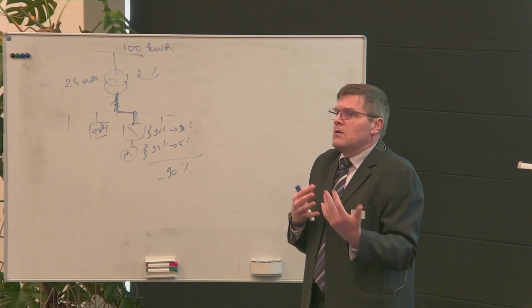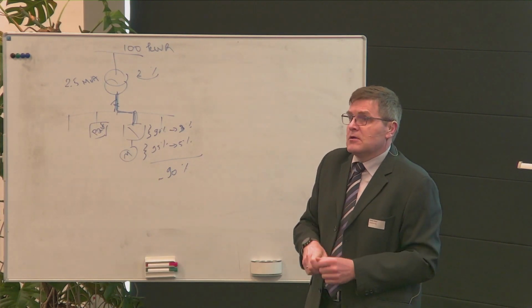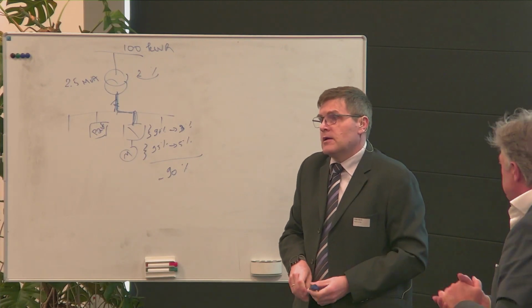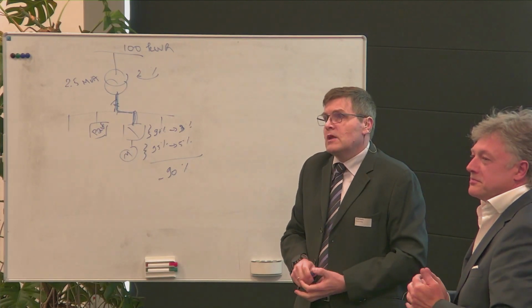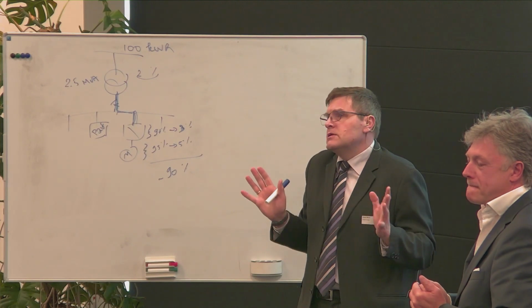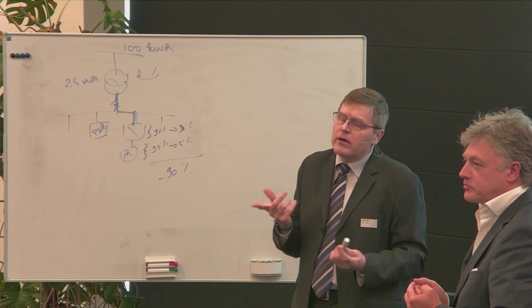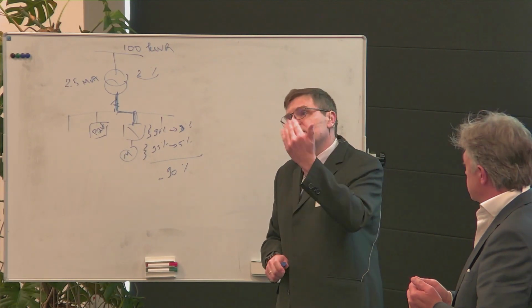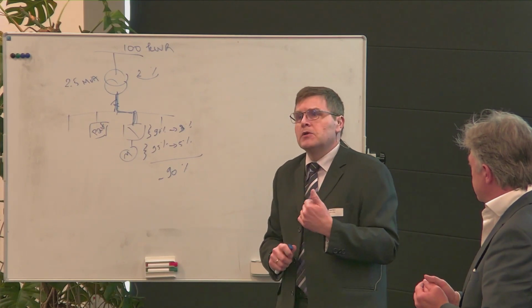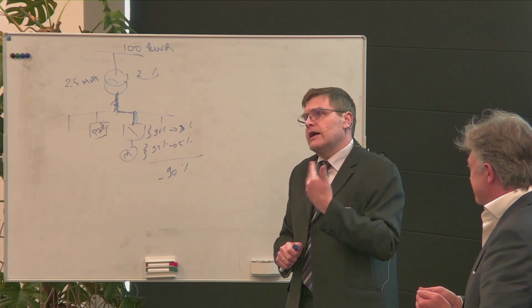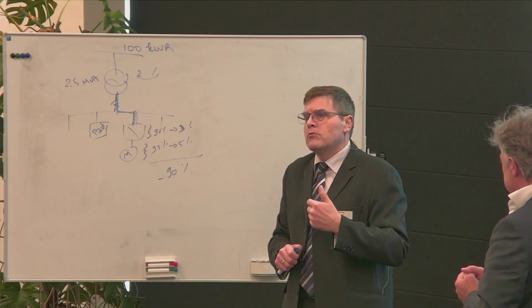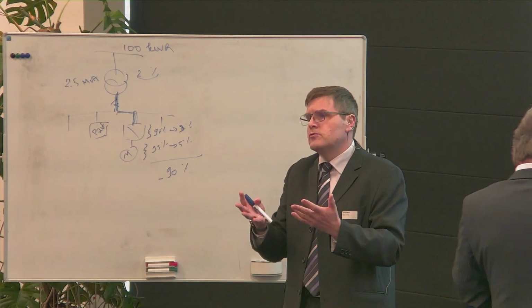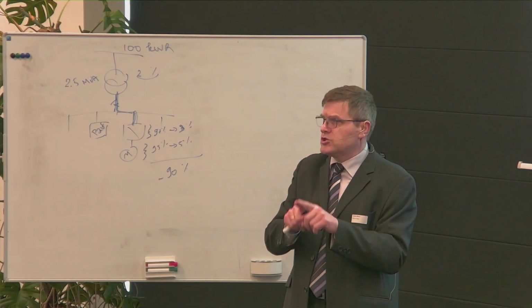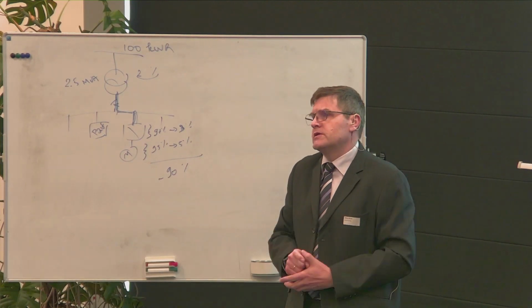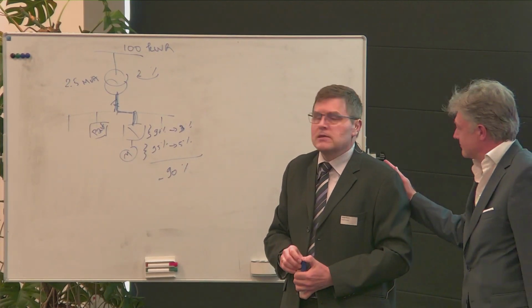So we have some cases where you reduce the active power on the grid. Active power is normally nearly the same. Yes, reactive power, yes. So here we have some savings and we can calculate them, but we will never tell you that an active filter will give energy savings. With power factor correction, yes, and we can calculate exactly.